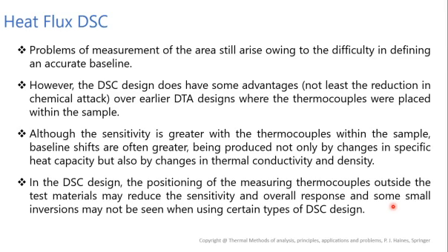Not least is the reduction in chemical attack over earlier DTA designs, where thermocouples were placed within the sample. Although the sensitivity is greater with the thermocouples within the sample, baseline shifts are often greater, being produced not only by changes in the specific heat capacity but also by changes in thermal conductivity and density.